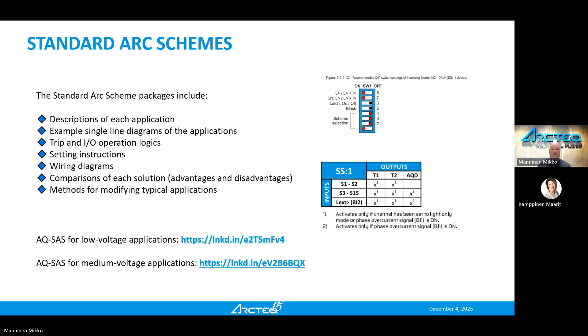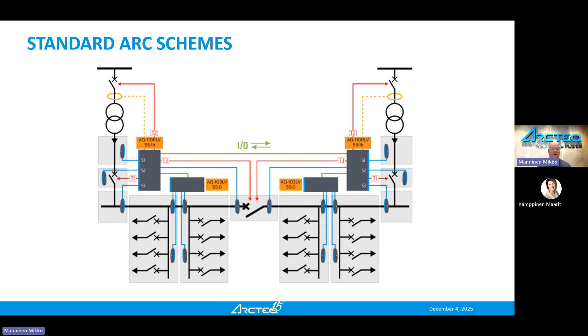From the standard applications you can find very simplified models like this one, for the main-tie-main low voltage application. You can use the simplified model to quickly identify if it's useful in your case, in your system. And once you see that this is exactly what you're looking for, you can find even more detailed diagrams with the trip matrix, dip switch settings, wiring diagrams, and pretty much everything. This makes it easy to adapt and configure exactly for your case and system.